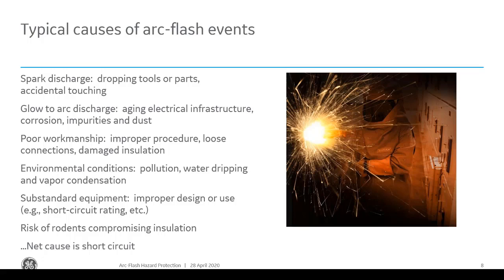Corrosion over time weakens the contact between conductor materials and terminals, increasing resistance through contamination and resulting in heat generation and sparks, which can obviously lead to arc flash events. Pollution on insulating surfaces also provides a path for current. Fumes and chemical vapors in the air can cause this too, so depending on your environmental condition, that plays a big part in the arc flash incident energy, as well as the number of arc flash incidents.